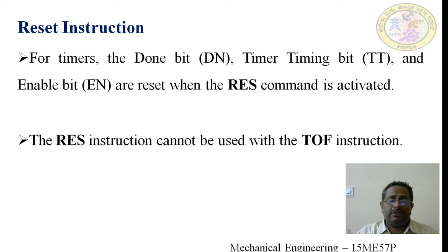For timers, the done bit, timer timing bit and enable bit are reset when the reset command is applied. It not only resets the accumulated value to 0, it also resets the done, TT and enable bits when it is activated. The RES instruction cannot be used with timer off delay. This is very important. It can only be used with TON, counter up, counter down or RTO, but it can't be used with the timer off delay, that is TOF.